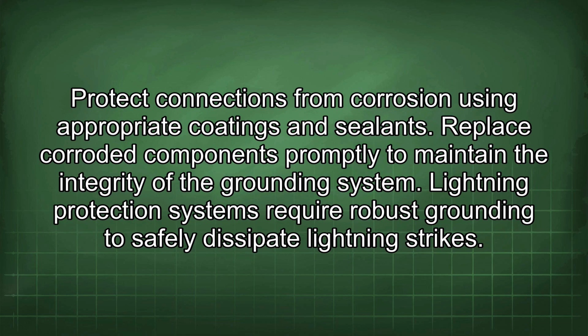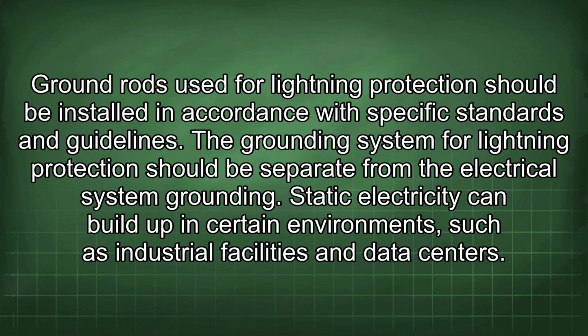Replace corroded components promptly to maintain the integrity of the grounding system. Lightning protection systems require robust grounding to safely dissipate lightning strikes. Ground rods used for lightning protection should be installed in accordance with specific standards and guidelines. The grounding system for lightning protection should be separate from the electrical system grounding.